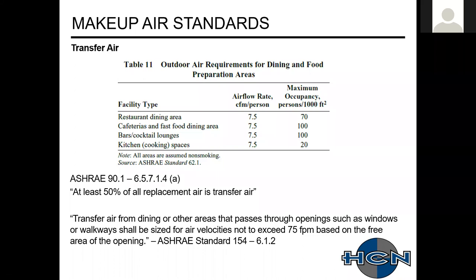There's a large chain restaurant, and this happens a lot too, that I saw before they started opening up their kitchen. Their pathway between the kitchen and the front of the house was just one doorway, and they supplied most of their makeup air out of the rooftop units. They were doing exhaust-only hoods, and they would get a wind tunnel effect. Anyone sitting right next to it could feel the air just rushing by. So those customers are not very comfortable. They opened up their kitchen to the space, and that solved a lot of their problem because they were able to reduce the velocity.